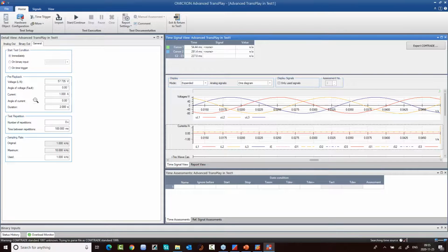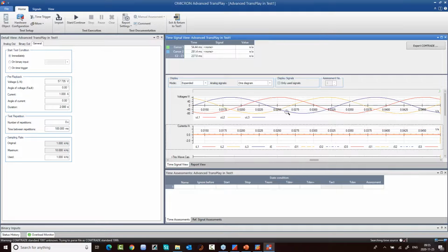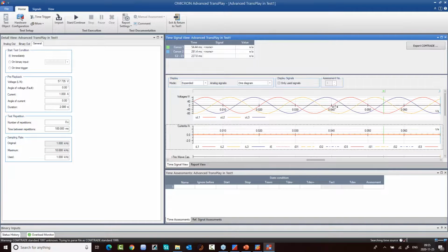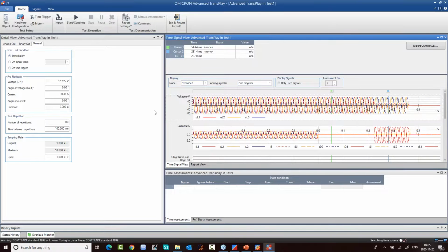And also this is sometimes recommended in some relays which require a pre-fault, and maybe by mistake the person who configured the disturbance recorder neglected this condition. Then you can overcome it by using this. Okay, this is the pre-fault for 2 seconds.